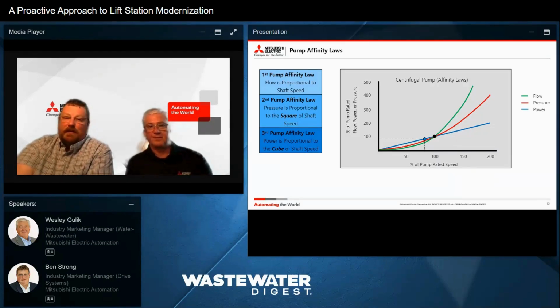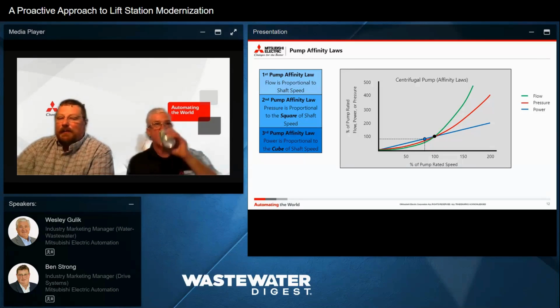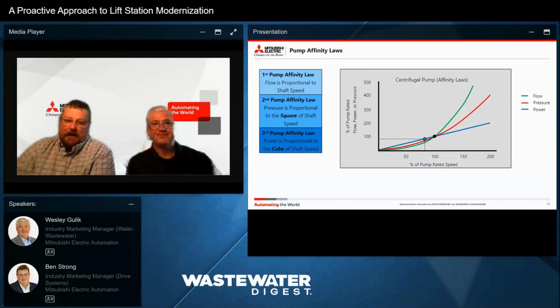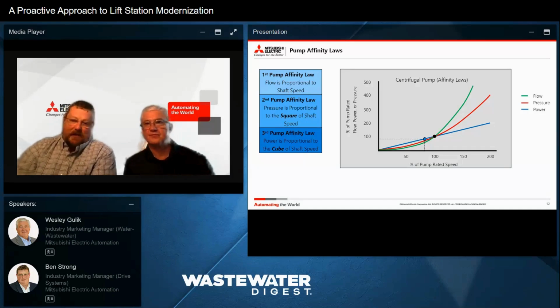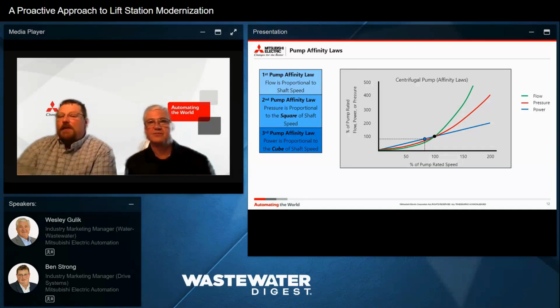So here, if you've been in wastewater, I'm sure you're aware of the pump affinity laws. But the point we're making here is, if we're comparing a pump that operates at 60 hertz across the line, we can't vary the speed, and therefore we can't vary the flow rate without a bypass or a throttle valve. A VFD, by comparison, allows us to operate and move the best efficiency point for that system back and forth.